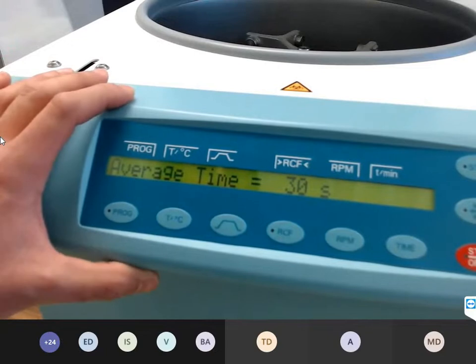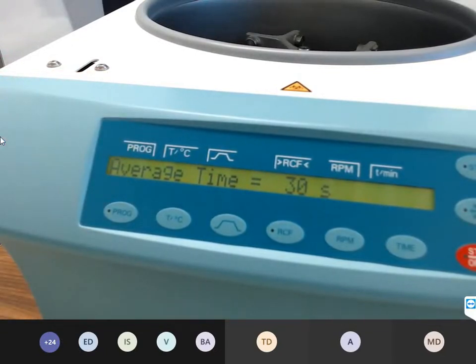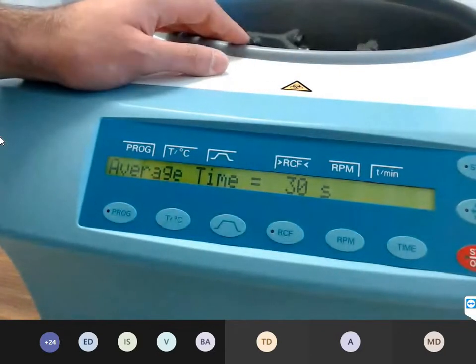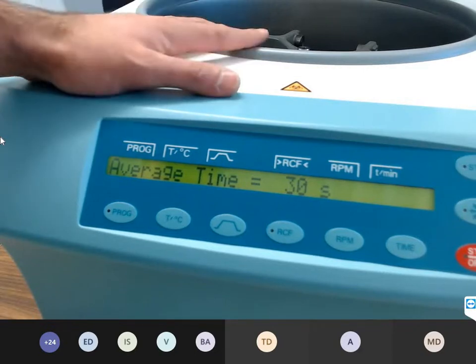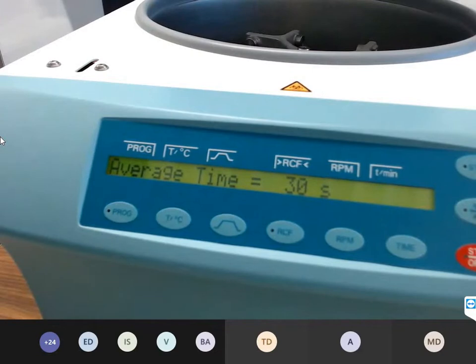Average time, that's maybe an important setting. You can set the average time from 0 to 180 seconds. That means in this time, for example 30 seconds, the display shows the real temperature. For example, you set 20 degrees. In this time, the centrifuge shows you the real temperature. After this time, you can see the right temperature. That's only the time you can change. 30 is the standard time, the manufacturing setting time.